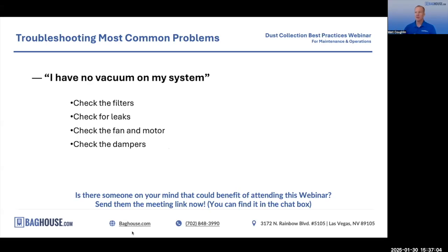So number one is the filters. It's a filter system, right? So just like Scott said, you have a filtration system with surface filtration where dust builds up on the filters. And as that dust builds up, the static pressure, or the resistance to airflow across that whole system, increases. So your fan might be pulling 10,000 CFM when you have 8 inches of static pressure in your system, but then now your filters are getting all clogged up with dust. So now you're at 12 inches of static pressure. So if you go back to a fan curve, you'll see that the CFM essentially decreases in correlation with that. So first thing we always look at is the filters.